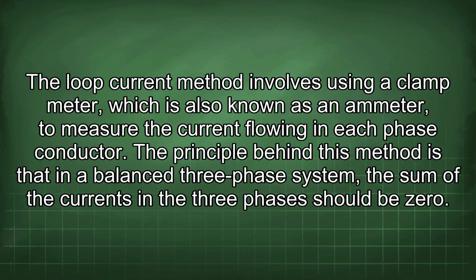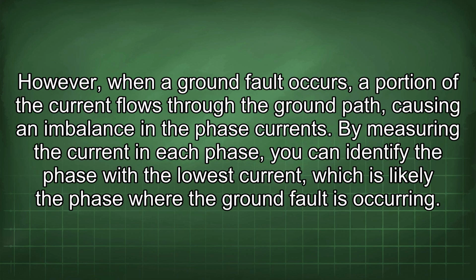The loop current method involves using a clamp meter, which is also known as an ammeter, to measure the current flowing in each phase conductor. The principle behind this method is that in a balanced three-phase system, the sum of the currents in the three phases should be zero. However, when a ground fault occurs, a portion of the current flows through the ground path, causing an imbalance in the phase currents. By measuring the current in each phase, you can identify the phase with the lowest current, which is likely the phase where the ground fault is occurring.